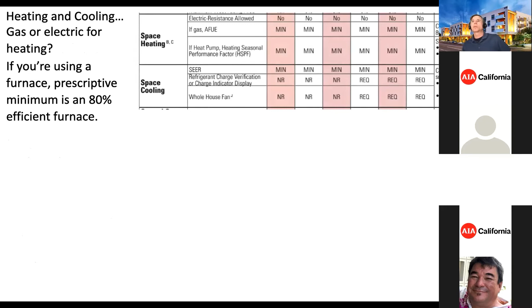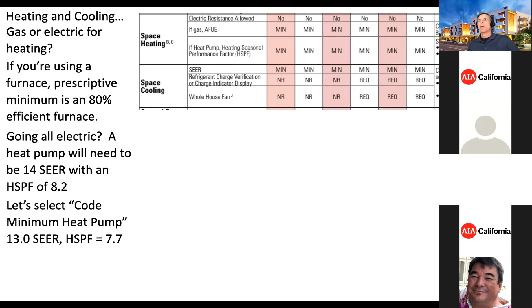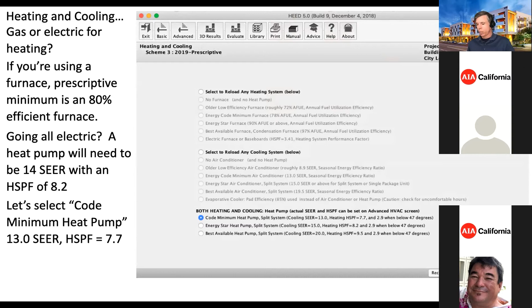Gas or electric, big conversation these days. If you're using a furnace, prescriptive minimum is an 80% efficient furnace. We'll talk about going all electric in a little while, but for an all-electric building, a heat pump will need to be 14 SEER with an HSPF, heating season performance factor, of 8.2. Higher the number, the better. For this one, I'm going with a code minimum of 13 SEER and HSPF 7.7. Even though they fall short, this one was built for a previous code cycle and hasn't been updated, and they don't have funding from the CEC to do that. So we're going with this for now, and we'll adjust to the 2019 requirements in a little while.